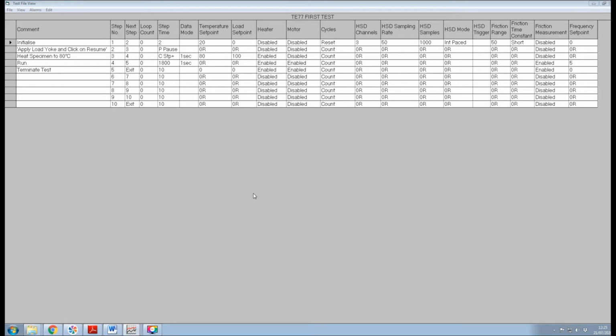The step time box now shows an abbreviation for conditional step positive, indicating that a rising value conditional step has been programmed. The test will now move to the next step once the specimen temperature equals or exceeds 80 centigrade.